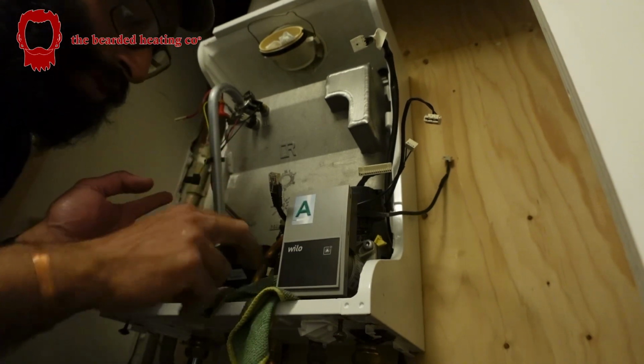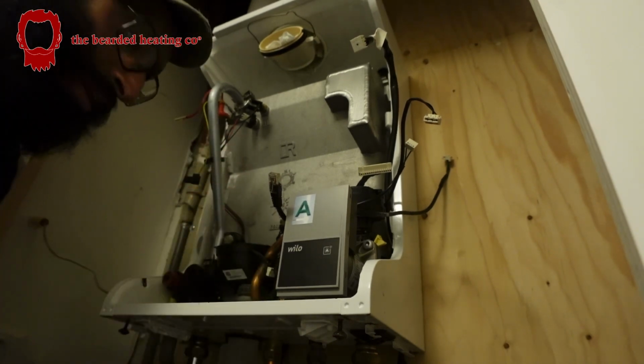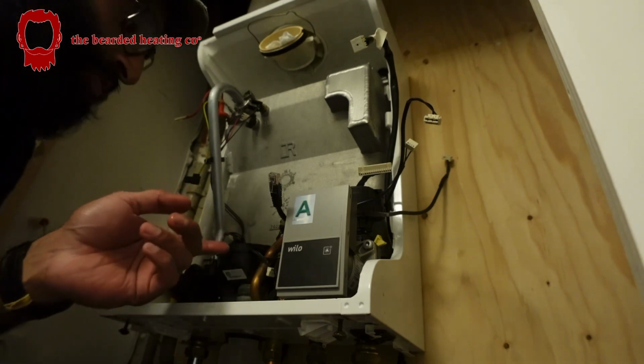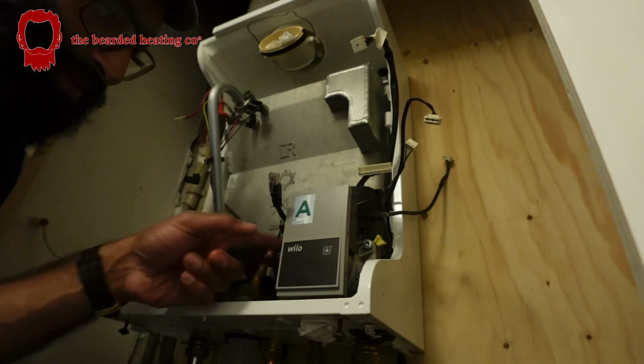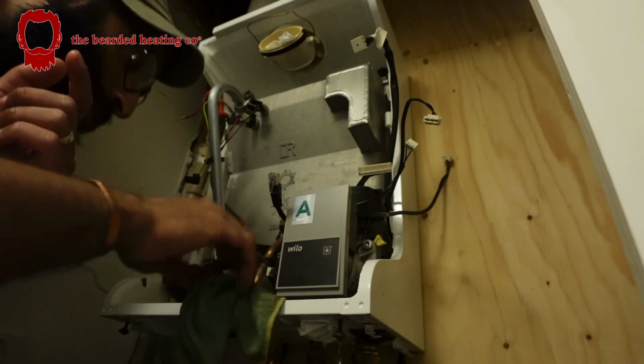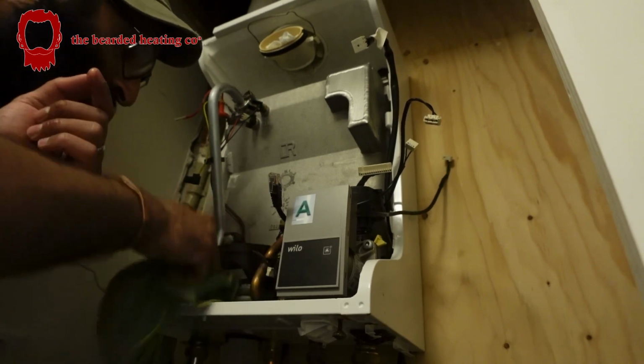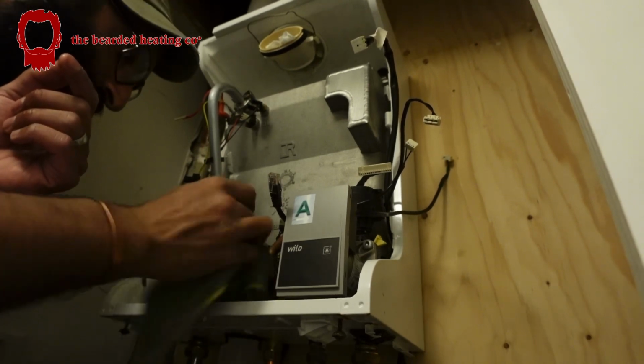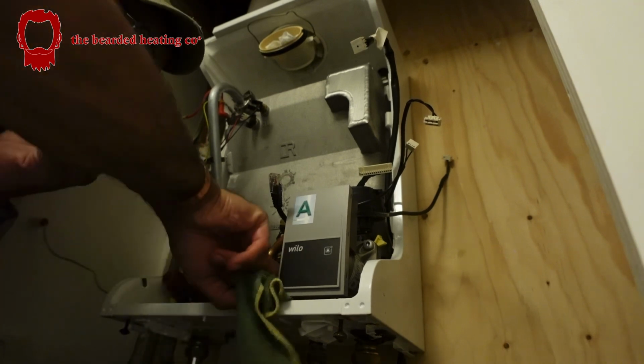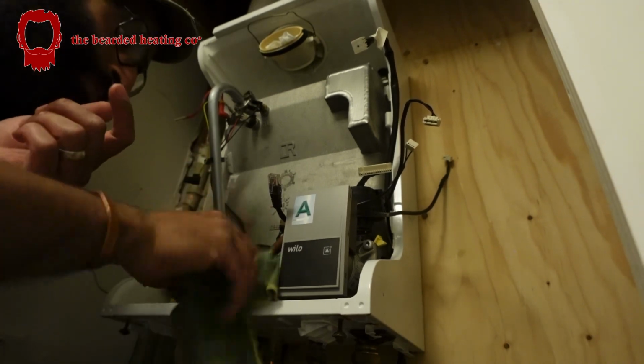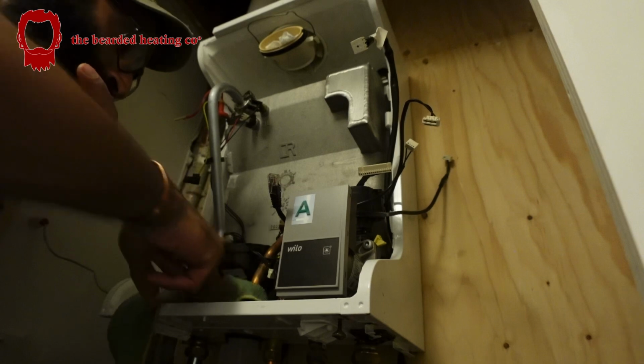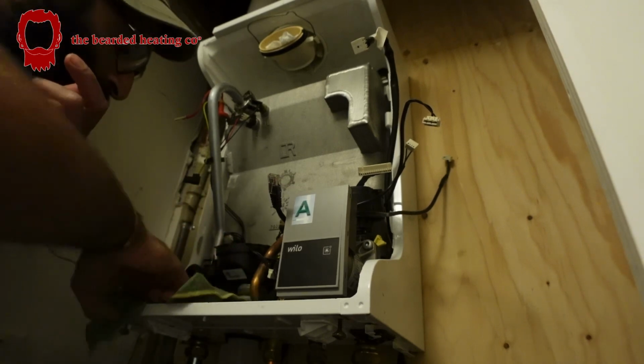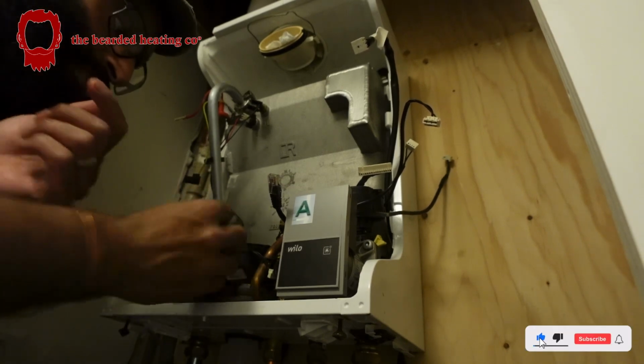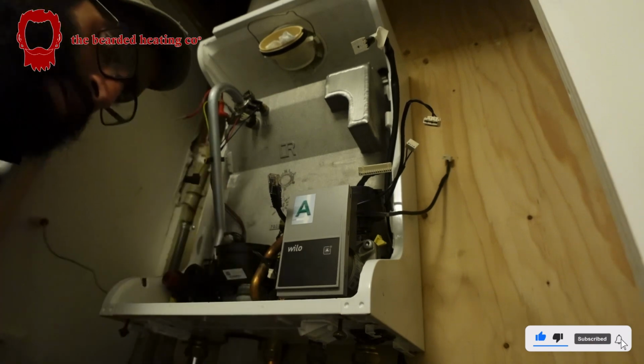The reason I knew it was the cold or hot water that's leaking was because, firstly, there's limescale built up on the hydro block, but mainly because the water was absolutely clear and literally drinkable, and the system pressure was not dropping at all. So I knew straight away it's got to be on the domestic water side and not the heating circuit.